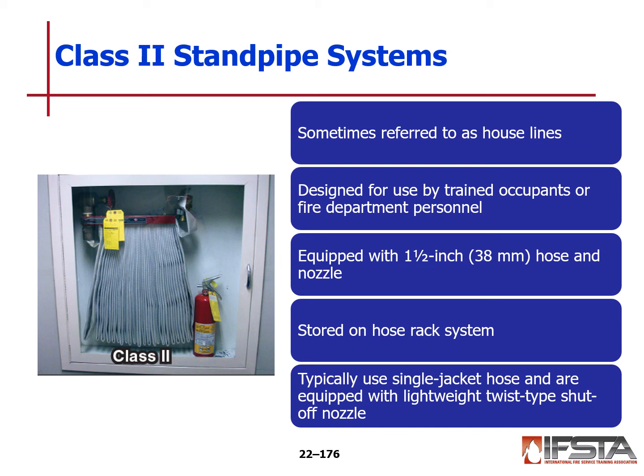A Class 2 system, sometimes referred to as house lines, is designed for the use of trained occupants or fire department personnel. They are equipped with 1.5 inch hose and nozzle, stored in a hose rack type system as you see in the photograph, and typically use single jacket hose and are equipped with lightweight twist type shut-off nozzles. One of the problems we encounter with this type of system is that they are rarely used, and oftentimes over the years the hose will dry rot and become inoperable. Oftentimes they are also damaged by vandalism and occupants of the buildings. These can be found in apartment buildings, and this is one of the areas that is heavily damaged. When we inspect apartment buildings and look at these common areas, when we find these, we should also inspect these hose systems to see if they are operable.